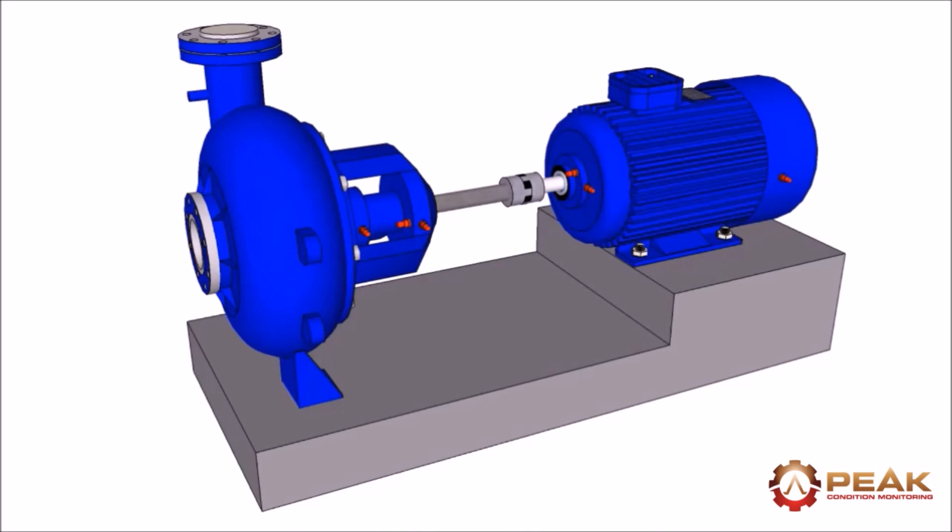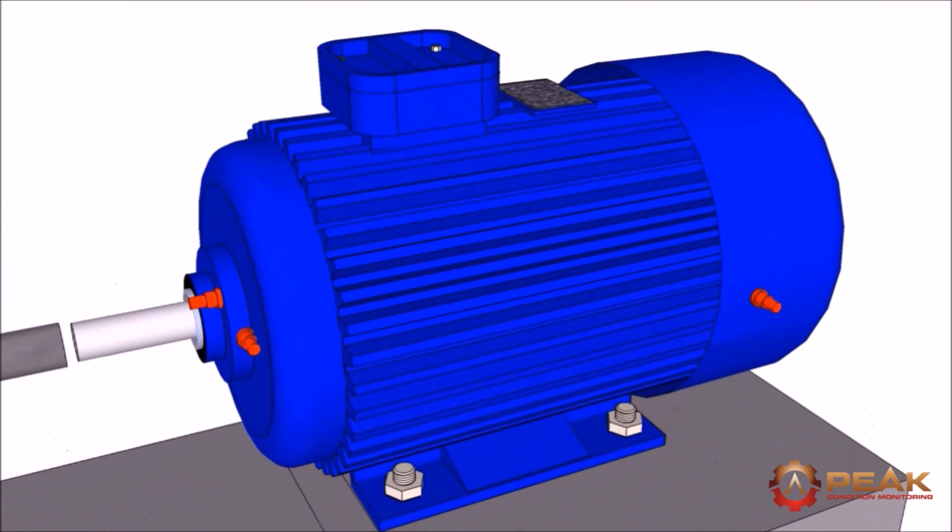In our first example we'll look at possible faults detected in this pump assembly. The problem is first picked up by a high 1x peak in the radial direction. To determine the source we decouple the motor coupling.